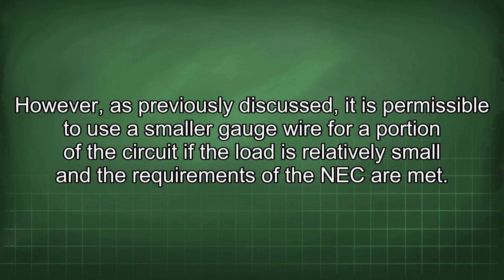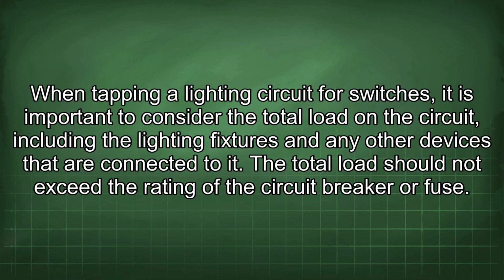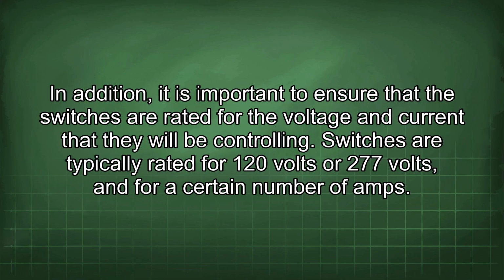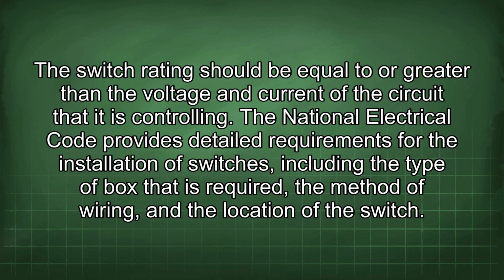However, as previously discussed, it is permissible to use a smaller gauge wire for a portion of the circuit if the load is relatively small and the requirements of the NEC are met. When tapping a lighting circuit for switches, it is important to consider the total load on the circuit, including the lighting fixtures and any other devices that are connected to it. The total load should not exceed the rating of the circuit breaker or fuse. In addition, it is important to ensure that the switches are rated for the voltage and current that they will be controlling. Switches are typically rated for 120 volts or 277 volts, and for a certain number of amps.